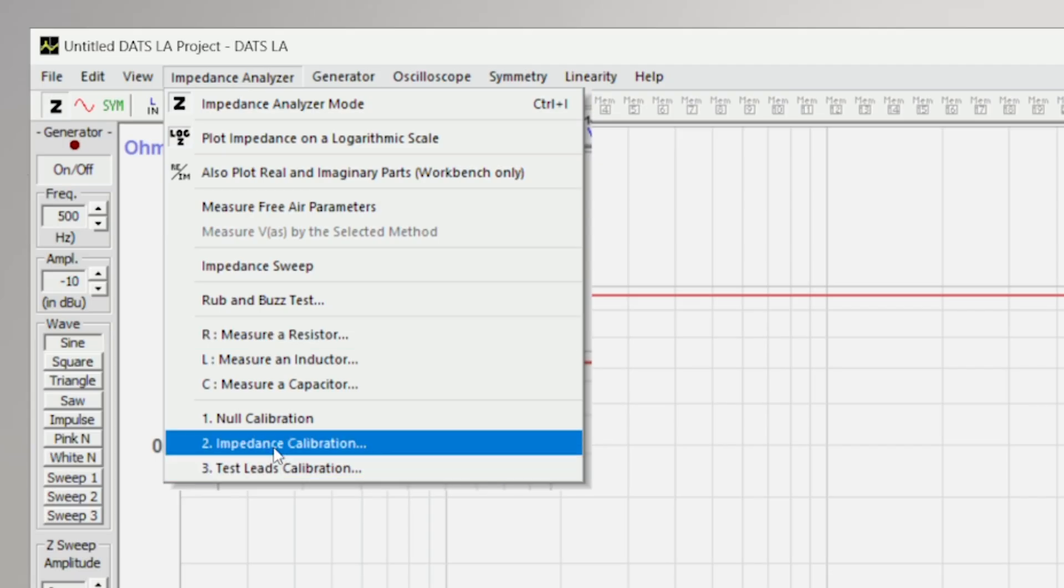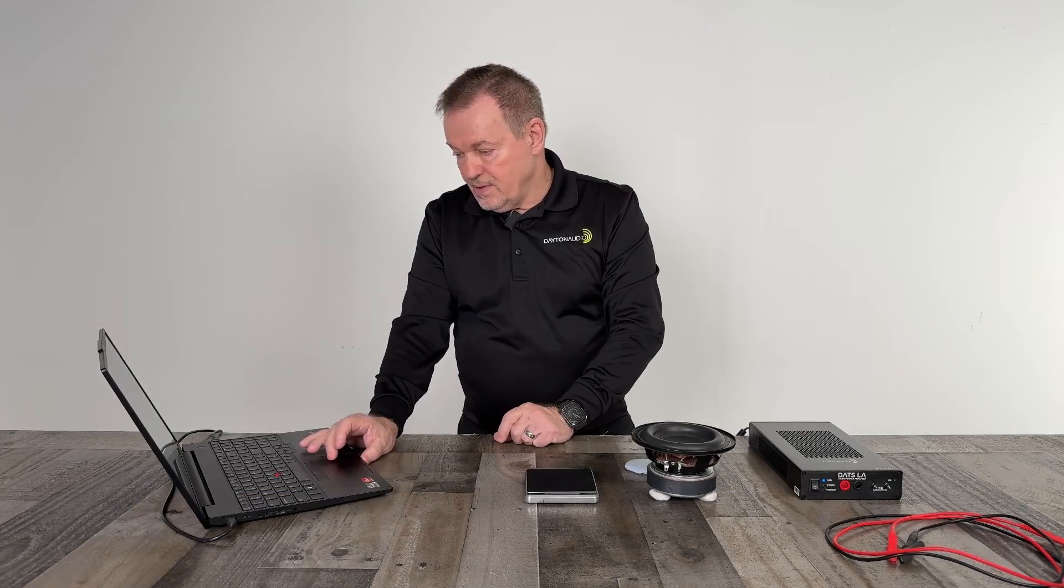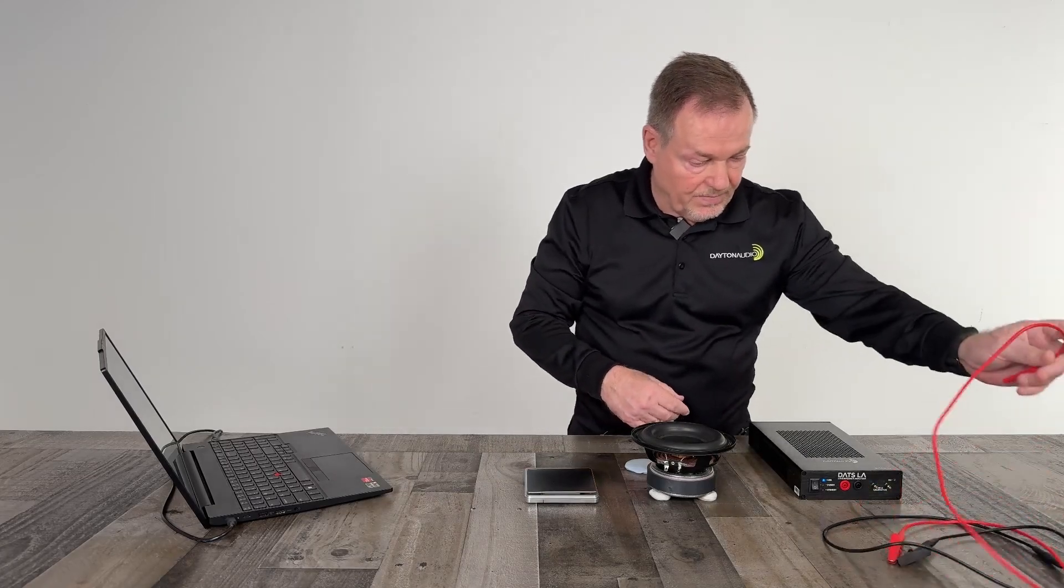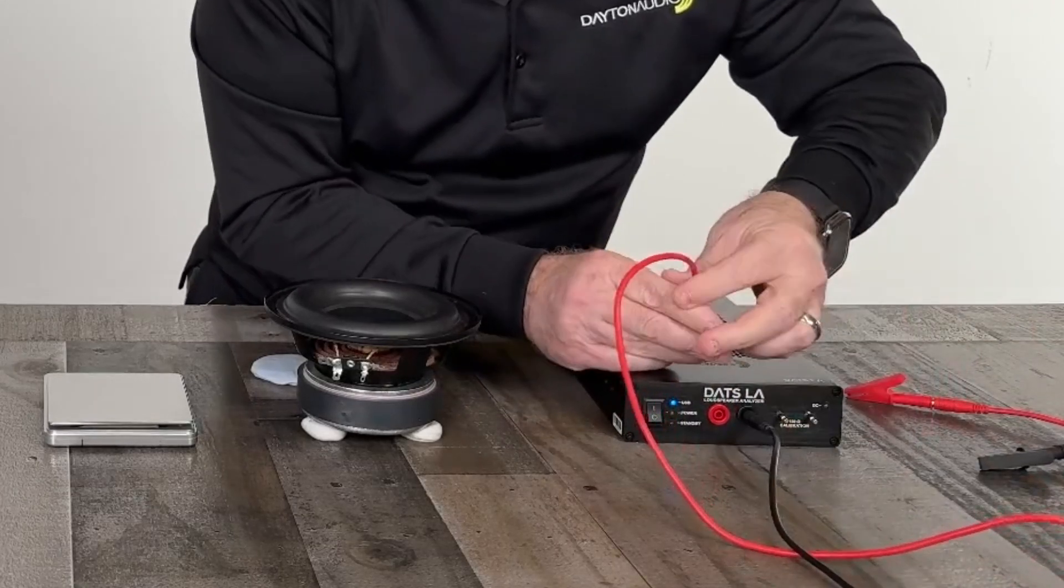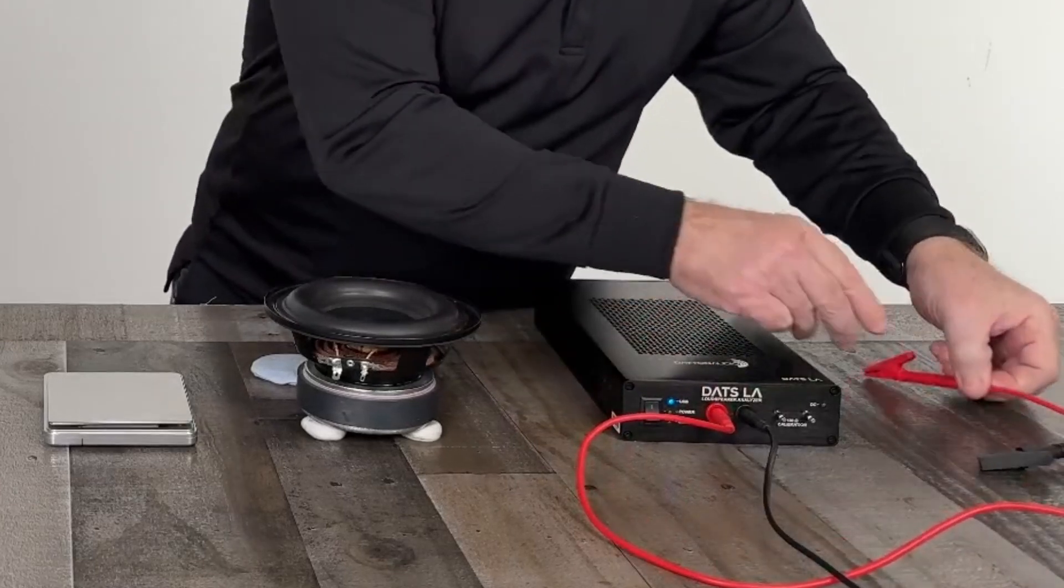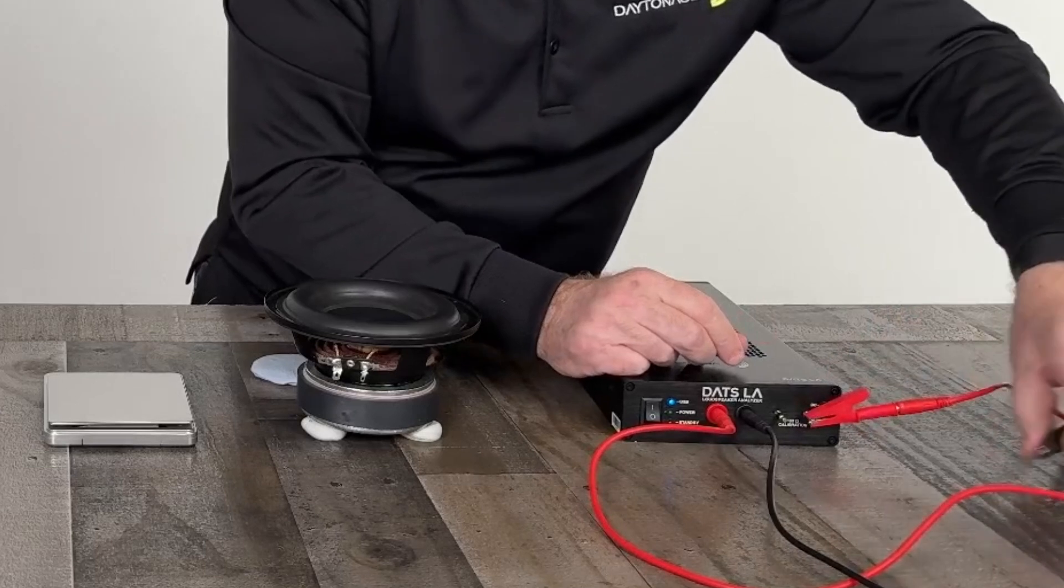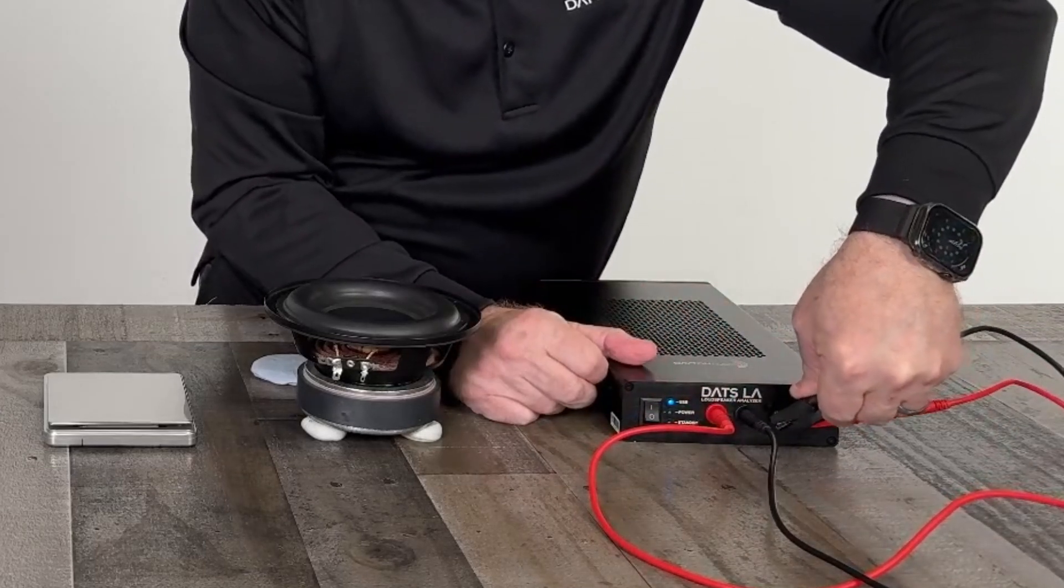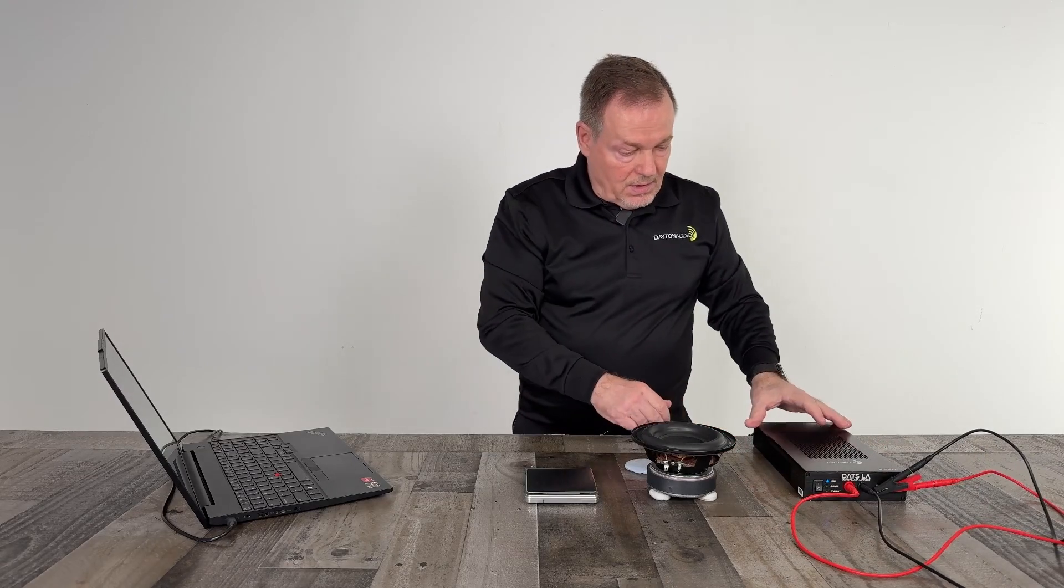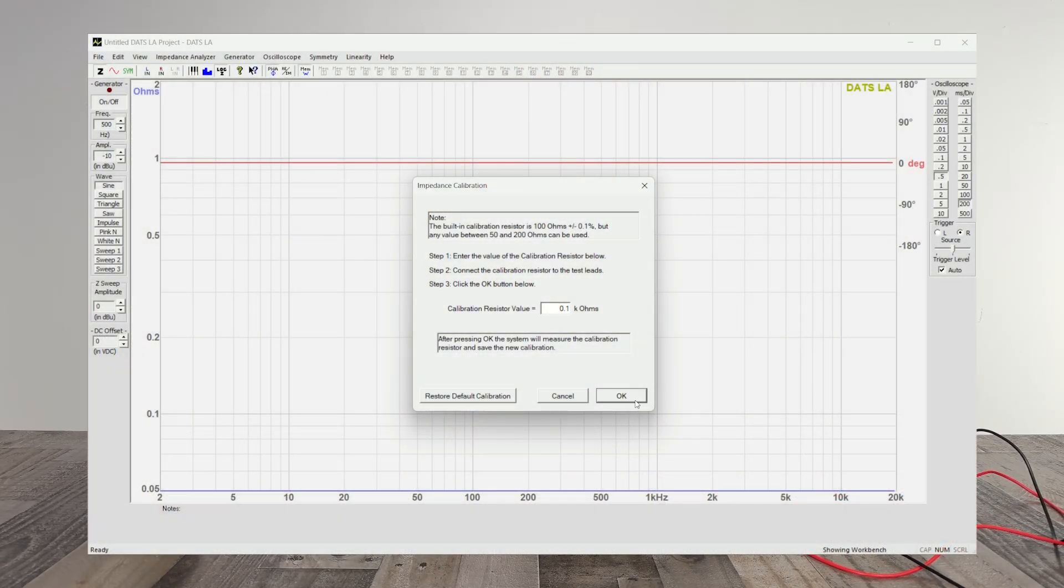Now it's going to prompt us to connect it to the supplied 0.1k or 100 ohm resistor. So we need to connect the insulated binding post, minding the polarity, securely fastened. Then we can connect the outer gator clips to the turret connections that has the 0.1 kiloohm 0.1% resistor.